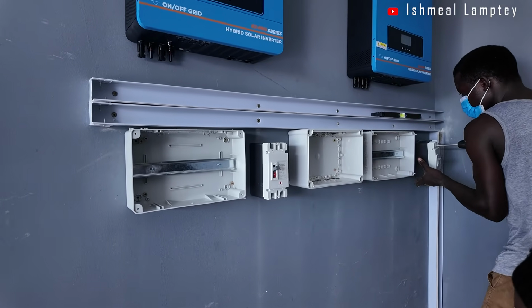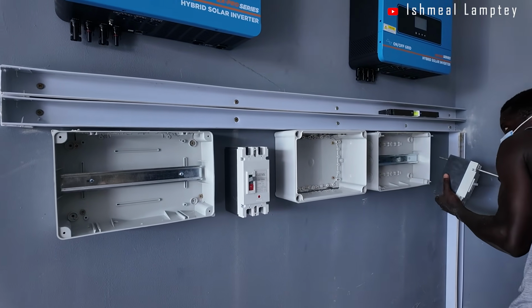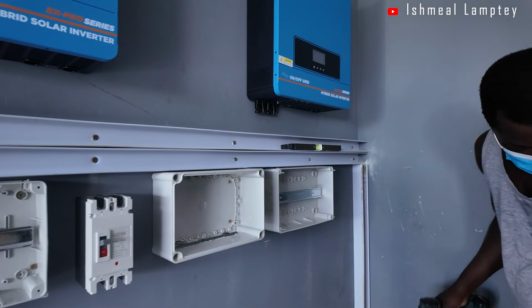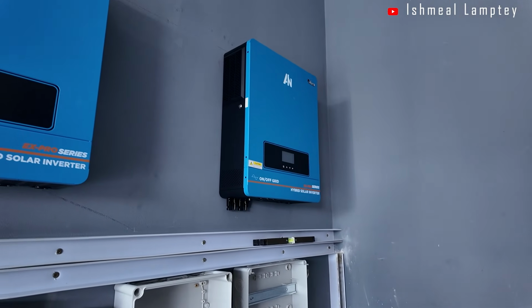I had to familiarize myself with the manual for both inverters as well as the battery, to know how to go about the configuration. The installation is usually in two parts: the hard part, where you mount the devices and route your cables, and then the actual configuration on the inverter itself - telling it the kind of battery you're using, the current you want the system to charge at, and the voltage you want as output for the house or system, among other things.